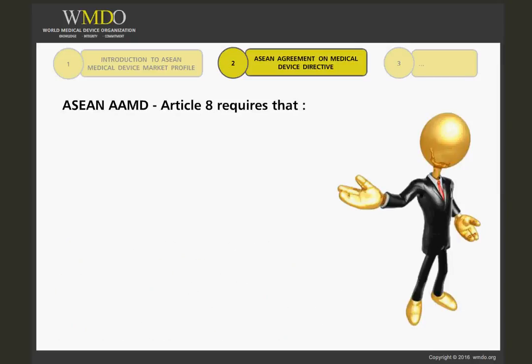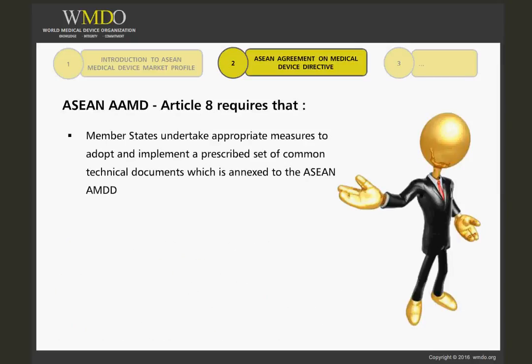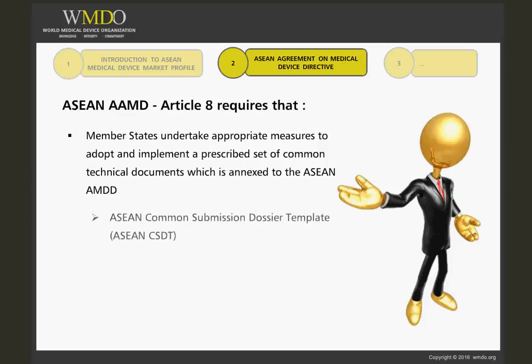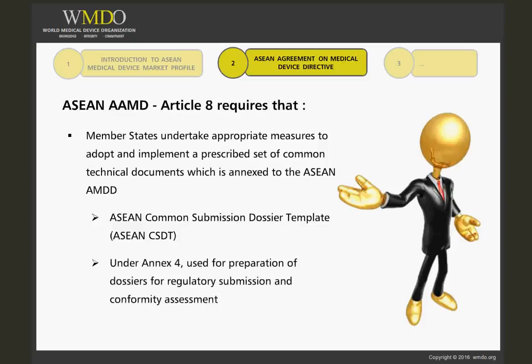Article 8 requires that Member States undertake appropriate measures to adopt and implement a prescribed set of common technical documents which is annexed to the ASEAN AMDD, one of which is the ASEAN Common Submission Dossier Template, or the ASEAN CSDT, under Annex 4. The ASEAN CSDT is to be used for preparation of dossiers for regulatory submission and conformity assessment.